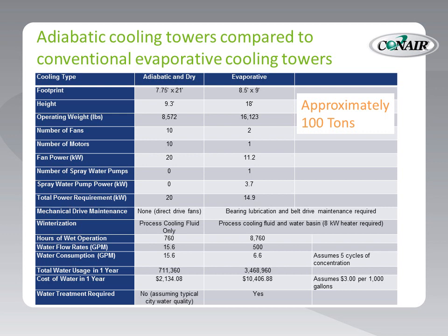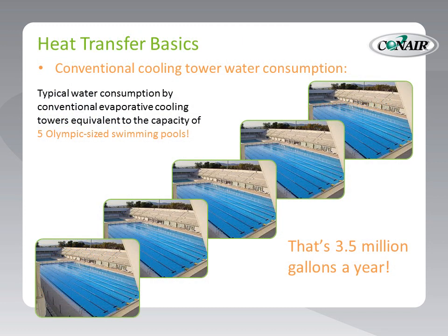Evaporative cooling towers are typically much taller, weigh a bit more, and require much more maintenance than an adiabatic cooler. But importantly, note the water usage differences. 3.5 million gallons of water will be used by the evaporative cooling tower. What does 3.5 million gallons look like? It looks like this — five Olympic-sized swimming pools full of water will be evaporated over the course of one year.